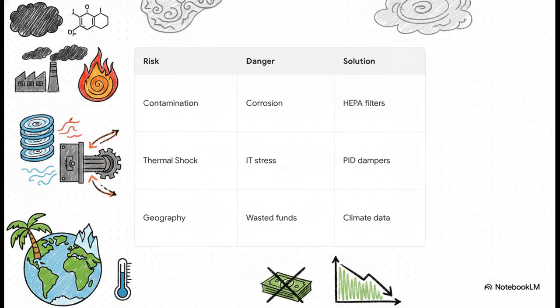Second is thermal shock. If a vent opens too fast on a freezing day, that sudden blast of cold air causes intense physical stress and instant condensation on the hot IT boards. So engineers use incredibly precise logic dampers to gently mix the air 1% at a time.